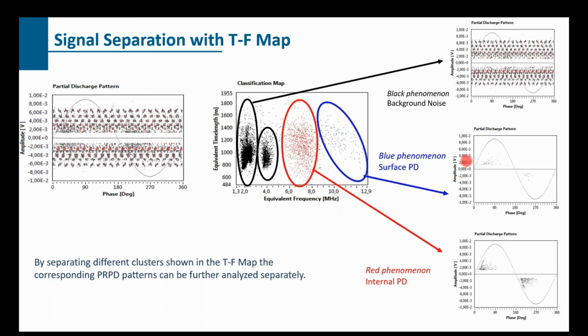And the blue group, we can see it has a unique pattern around here. Later on, we'll talk about how we recognize the type of discharge or the type of defects from the phase resolved patterns. It was recognized as surface discharge. And also the red group. The red group is another type of discharge, which is different from the blue cluster. The phase angle is different. The PD pattern is a little bit different. It has a little bit of rise on the edge. We call it rabbit ear. So it is a typical internal discharge.